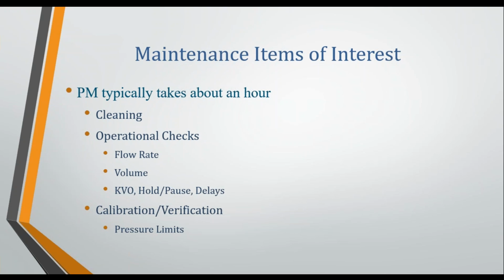We good? All right. Now, typically a PM, I mentioned this earlier, I think, a little bit. A typical PM is going to take about an hour or so. What's going to determine, to be honest, the biggest determinant of how long your PM is going to take you is how much cleaning you need to do. If the operators throughout the year have been diligent about cleaning the system off, which they are supposed to do, it tells them, the operator, clean daily, weekly, monthly, and annual. If they are doing that, then it really will make your life a lot easier.